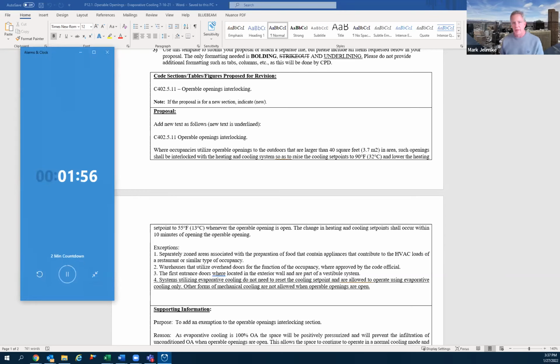One of the interesting things about evaporative cooling is that you can marry it up with direct expansion mechanical cooling. When they're appropriately controlled, the mechanical cooling only comes on for an appropriate trim of the evaporative cooling temperatures.